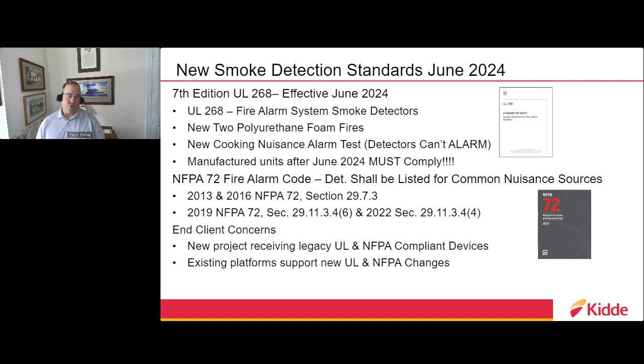UL is the independent testing laboratory for fire and life safety products, along with products in other industries. They changed their testing requirement back in 2015, requiring manufacturers of system smoke detectors, as well as smoke alarms like the 120 volt AC powered battery backup smoke alarms in single family homes, to make these detectors resistant to cooking—smoke or steam generated from cooking. The detectors are supposed to have the intelligence to stop, think, and look at the particle size within a chamber to understand what's happening.